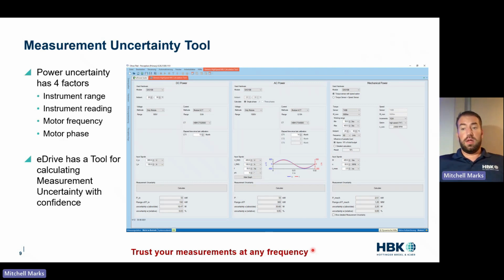And lastly, the accuracy of electric power is a mystery to a lot of people because it's honestly quite a pain. You have 4 factors that influence your power accuracy: instrument range, instrument reading, motor frequency, like we just discussed, and the phase between voltage and current. So HBK has supplied a measurement uncertainty tool for both mechanical power for your torque sensor and for AC and DC power. Basically, you enter the range of your amplifier, you enter the frequency, and you enter the phase, and we tell you what the uncertainty will be. So this gives you the ability to be quite confident, again, at these high frequency measurements, these high fundamental measurements, that you at least know what your uncertainty is.